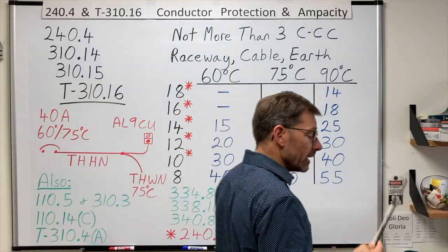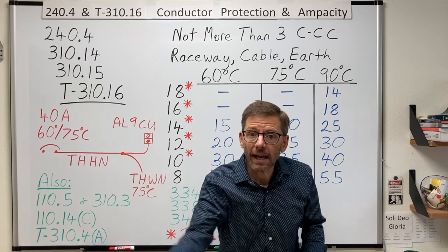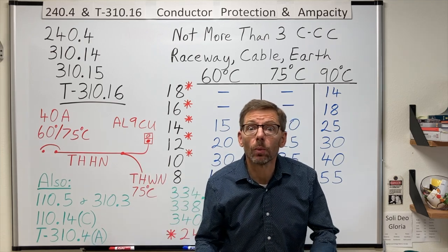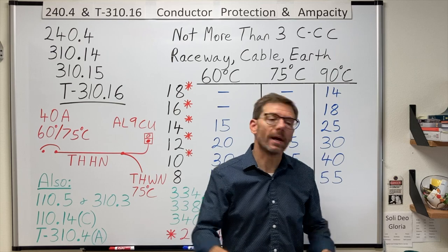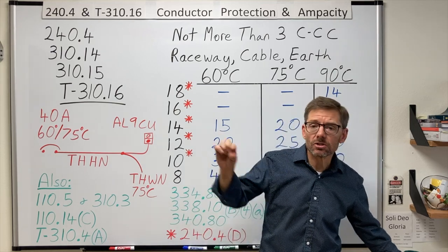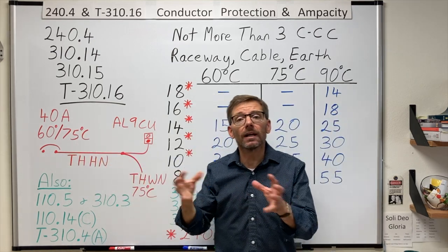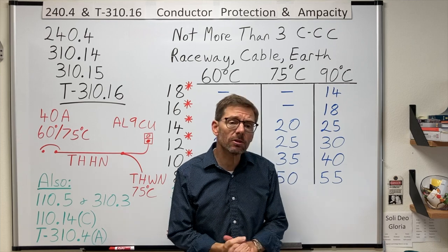But the main point I'm trying to make is this dual rating of the wire. So therefore, that conductor that you were thinking was THHN actually can be pulled underground or in a wet environment because it's rated for that as well. So look at the wires. Those ratings are listed every couple of feet along the wire. And also look for the temperature ratings of what you're connecting to. So consider those things.